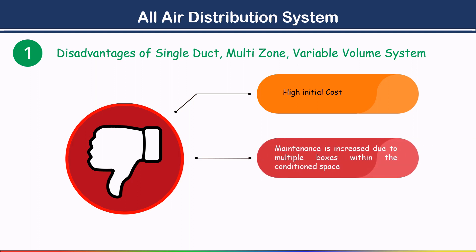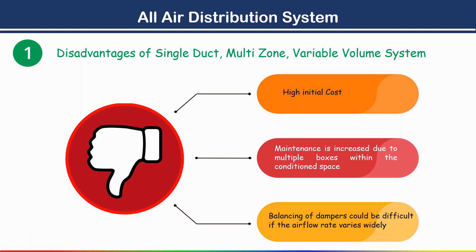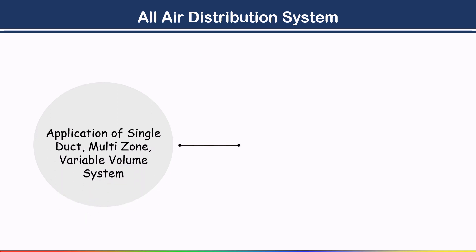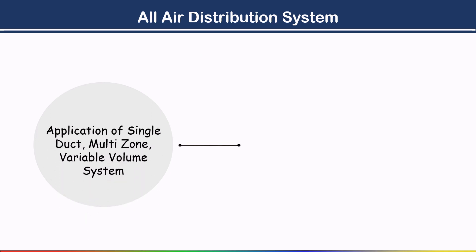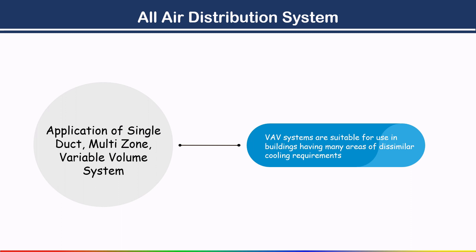Second disadvantage: maintenance is increased due to multiple VAV boxes installed at each branch before each room. Third, balancing of dampers could be difficult if the air flow rate varies widely. Regarding applications, VAV systems are suitable for use in buildings having many areas with dissimilar cooling requirements.